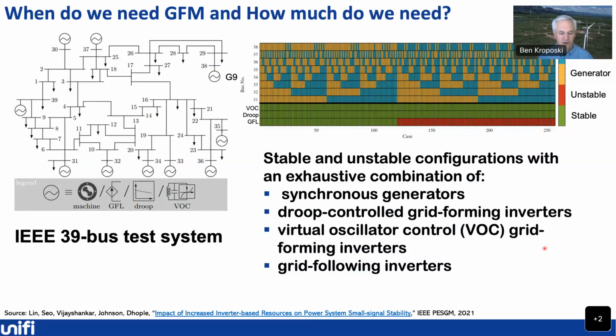First off is a group associated with the UNIFI Consortium, where they took a look at an IEEE 39 bus test system. So for people that are familiar with doing studies on power grids, this is a very well-known test system. It's got several generators scattered throughout a large integrated transmission system. And what they did was take a look at this and replace the various generators on here with either synchronous machines or grid following inverters or grid forming inverters with either droop control or virtual oscillator control. This graph up on the top is basically showing that they ran roughly 250 cases and deploying a variety of different technologies. The key thing here, as you can see in the coloring, is it's a very big mix of generators and inverters all scattered at different buses and at different levels.